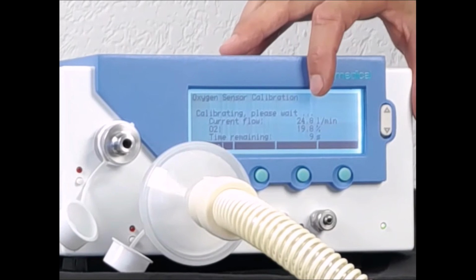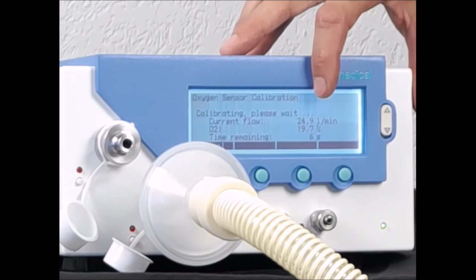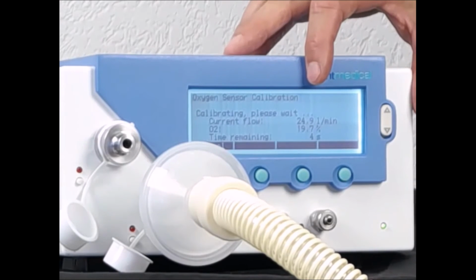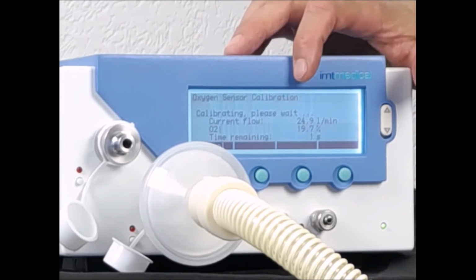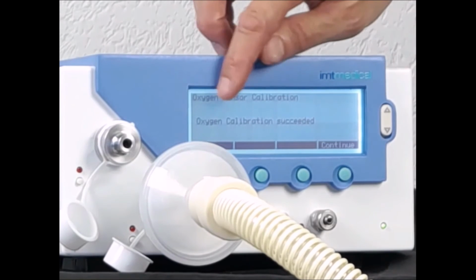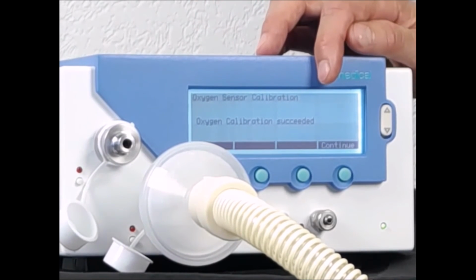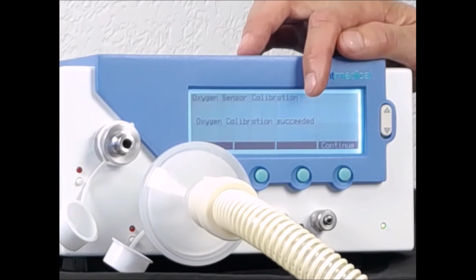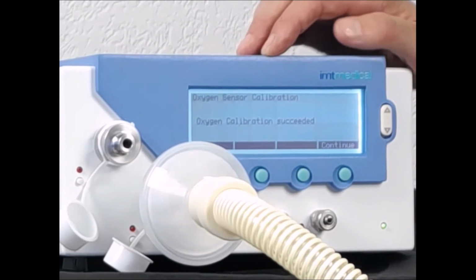So our oxygen calibration is right about to be finished. We have 8, 7, 6 seconds to go. That was the 21% oxygen point. And after this, our oxygen sensor calibration has been successful. I would like to stress the point that the oxygen sensor must be calibrated with a flow. The 25 liters per minute is really important to provide the oxygen sensor inside the PF300 with the necessary flow. It is not enough to just have a little bit of flow. It really needs 25 liters per minute.